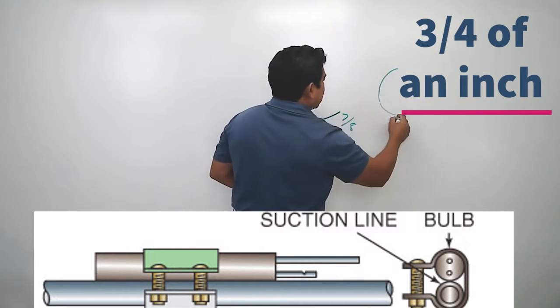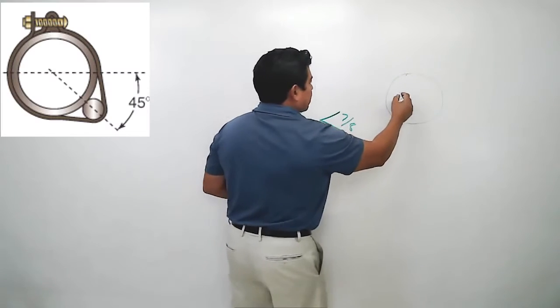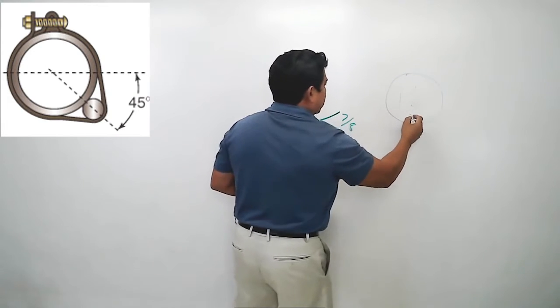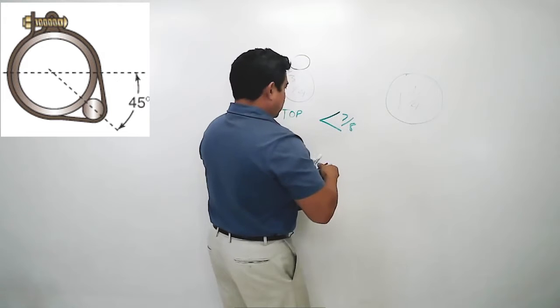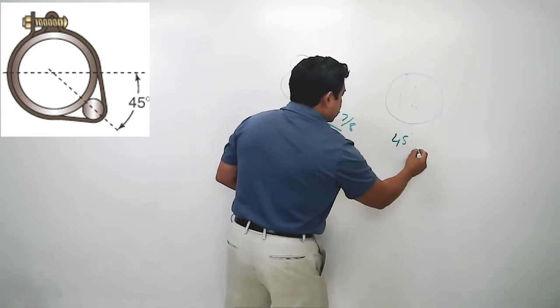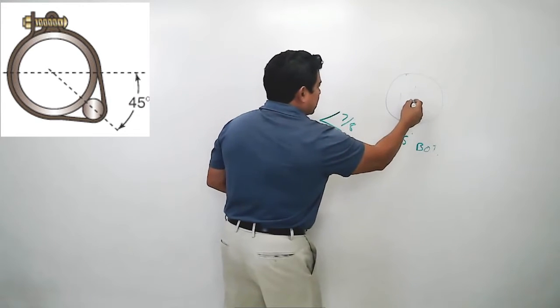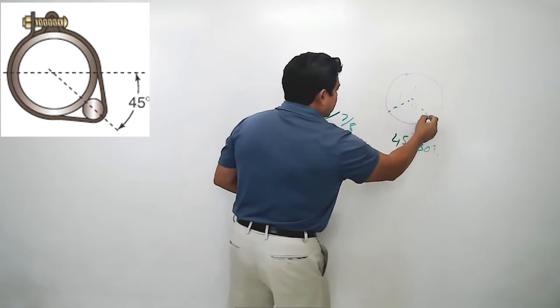If the suction line happens to be greater than seven eighths, let's say for example one and a quarter inch, then it's going to be 45 degrees from the bottom. So we can either place it here or we can place it here.